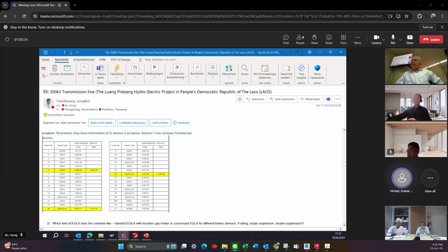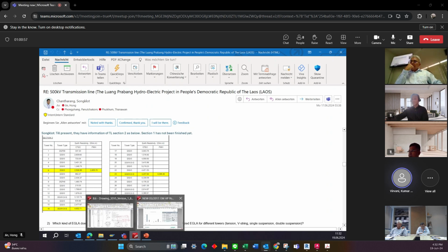Here I can also see that the information given against each tower is basically mentioning the resistivity and not directly the tower footing resistance. So we may require information about the earthing foundations, like the method of earthing, so that we can estimate the overall tower footing resistance based on the type of method used for the earthing and the different resistivity at each tower.